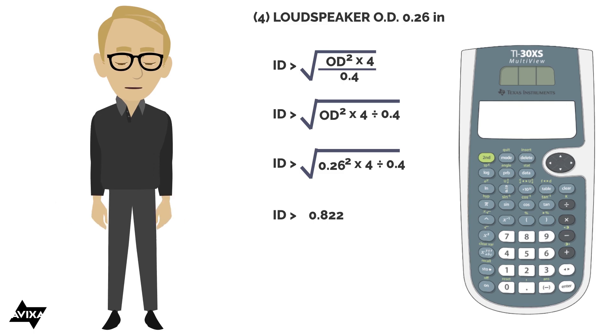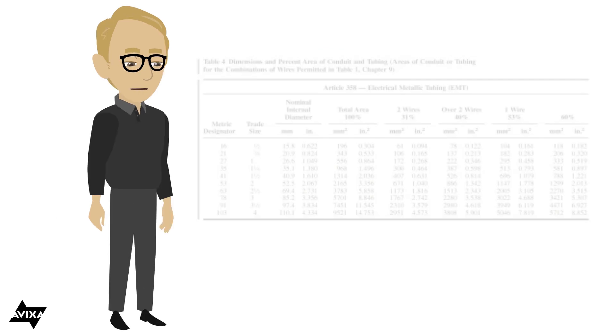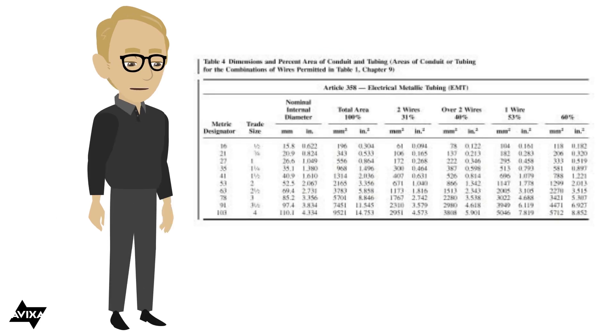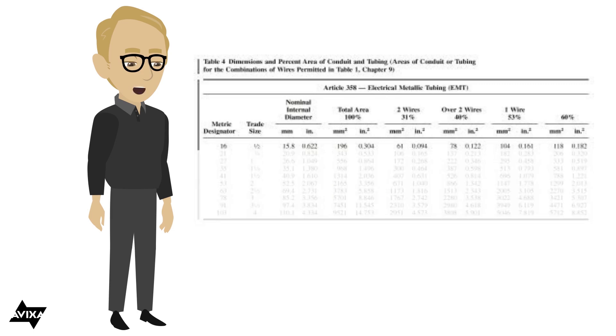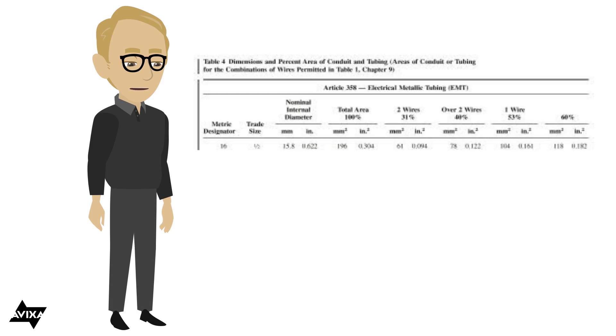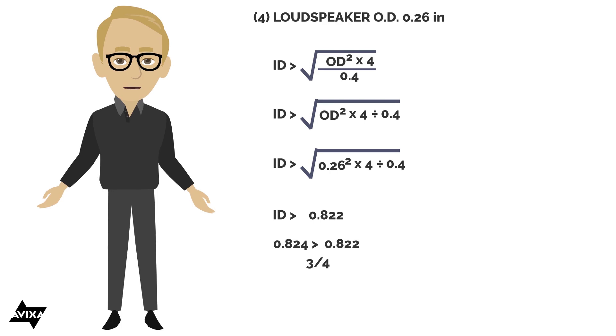I'll take that 0.822 result and compare it to available conduit sizes. A trade size one-half has an inner diameter of 0.622 — that's too small. A three-quarter has 0.824. Since 0.824 is larger than 0.822, that would actually work. So in this particular case, I can use the three-quarter conduit.